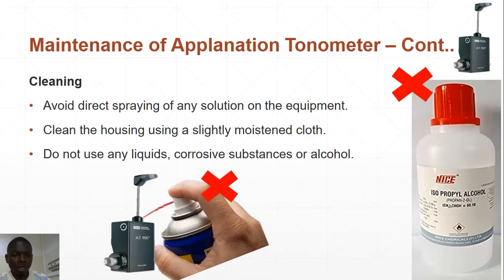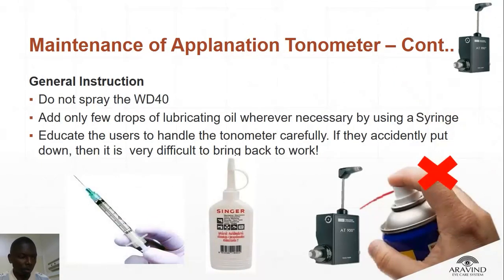Cleaning. While cleaning the tonometer, one must avoid directly spraying cleaning solution on the equipment. Very important. Clean the housing using a slightly moistened cloth. Very important. Do not use any liquid which is corrosive or alcoholic in nature. Corrosive means the material of the body of the tonometer gets damaged. Now we look at some general instructions regarding the maintenance of the tonometer.